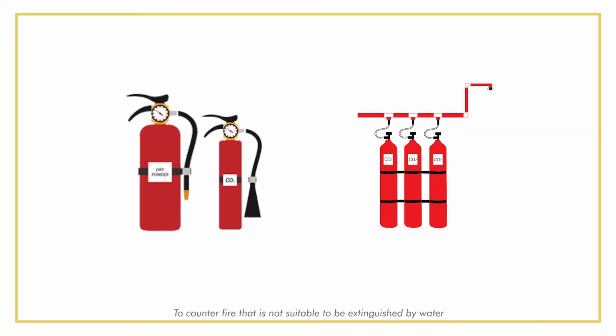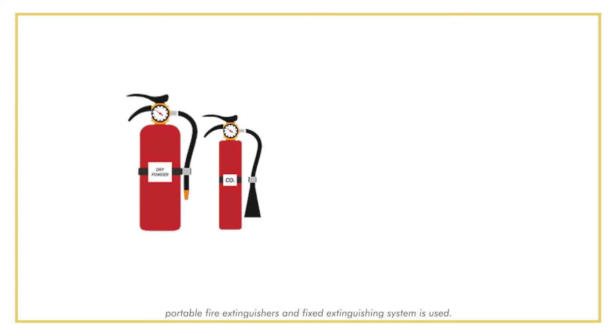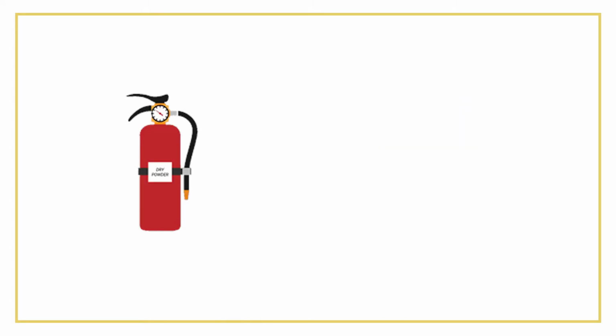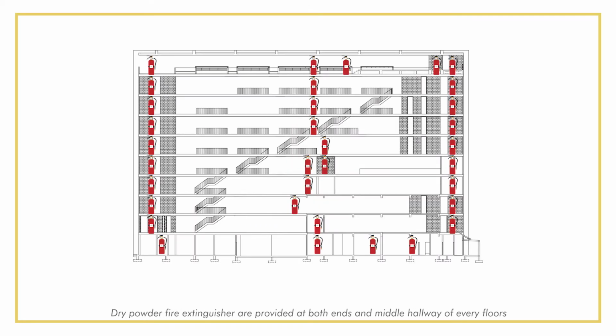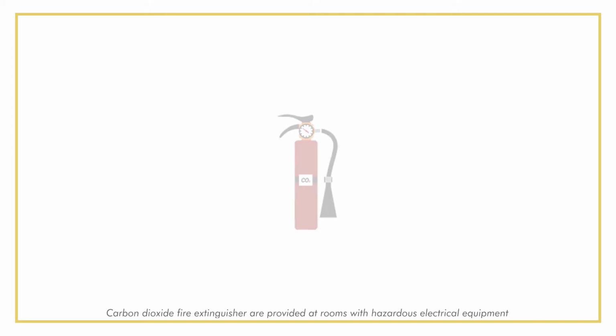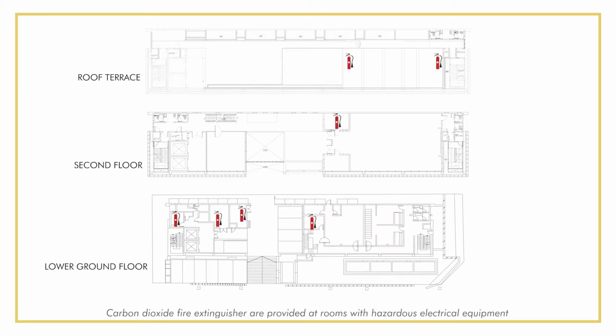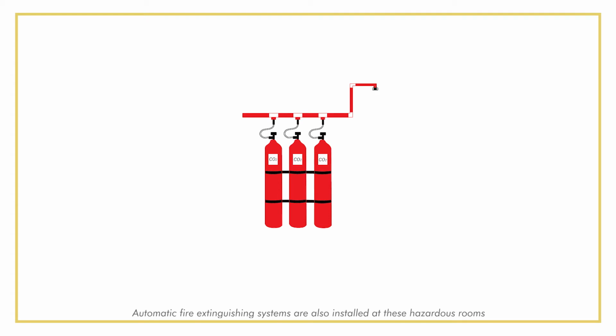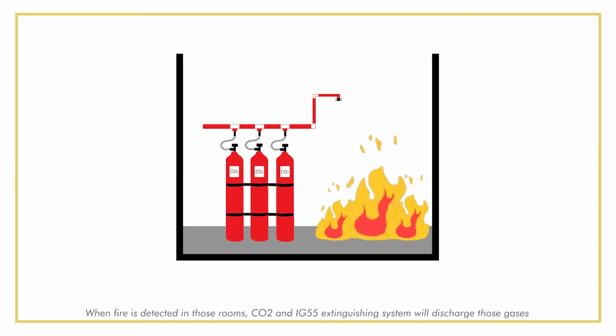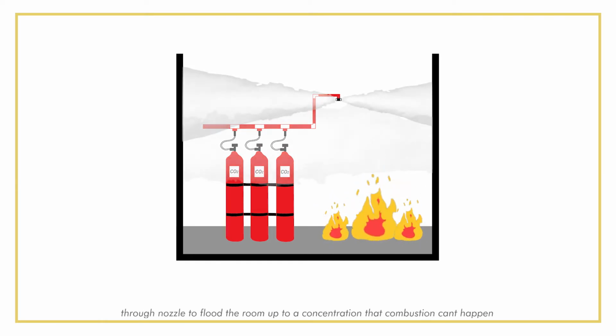To counter fire that is not suitable to be extinguished by water, portable fire extinguishers and fixed extinguishing systems are used. Dry powder fire extinguishers are provided at both ends and middle hallway of every floor. Carbon dioxide fire extinguishers are provided at rooms with hazardous electrical equipment. Automatic fire extinguishing systems are also installed at these hazardous rooms. When fire is detected in those rooms, carbon dioxide and IG-55 extinguishing system will discharge those gases through nozzles to flood the room up to a concentration where combustion cannot happen.